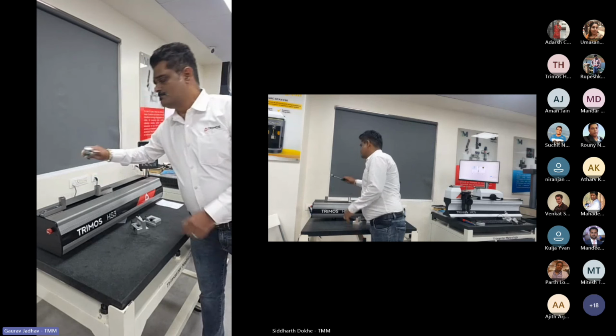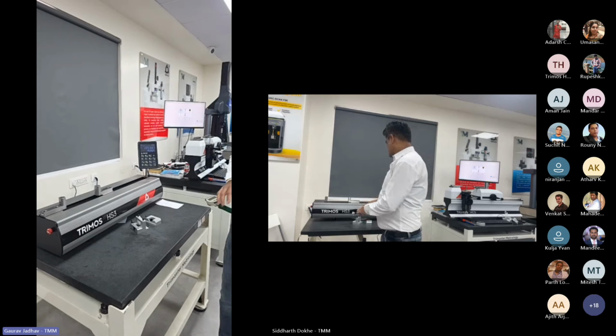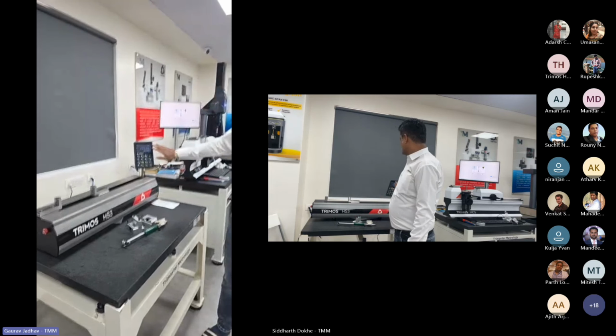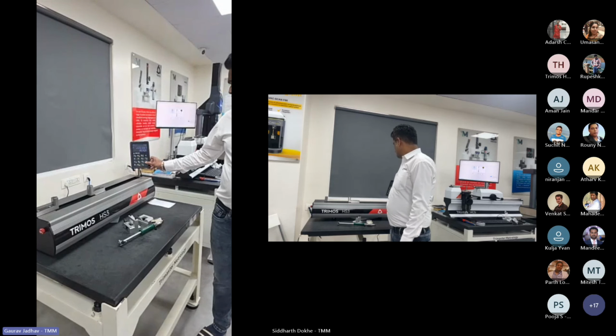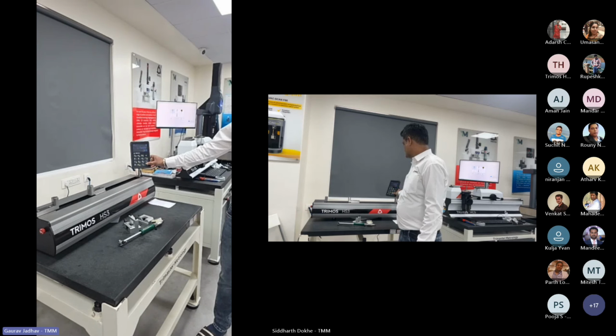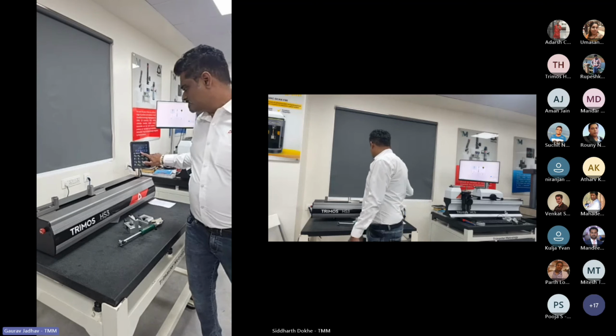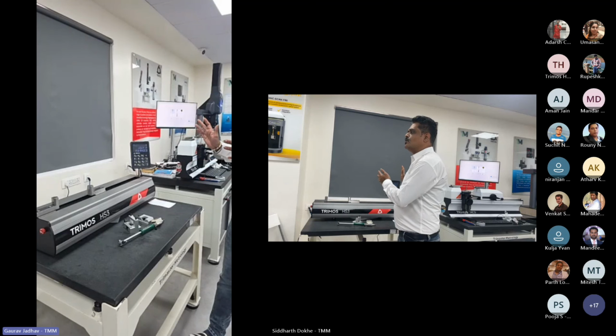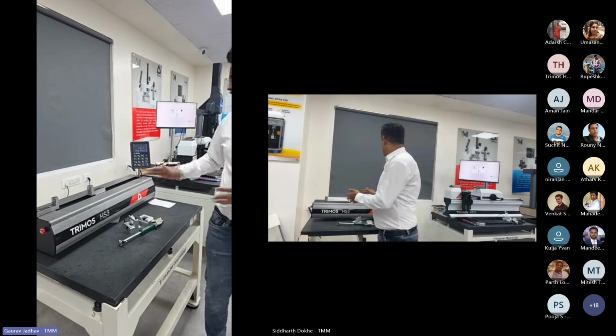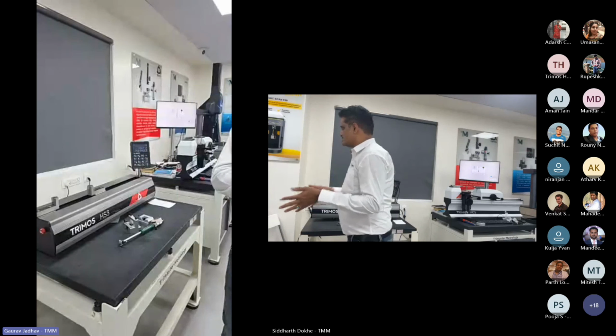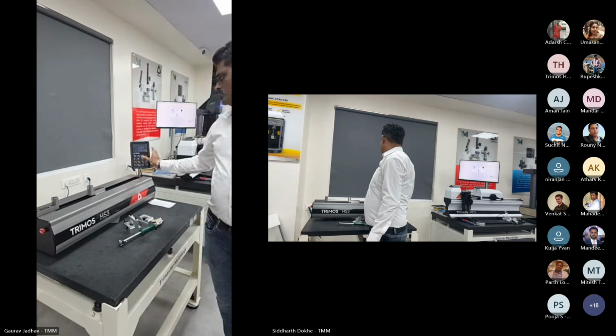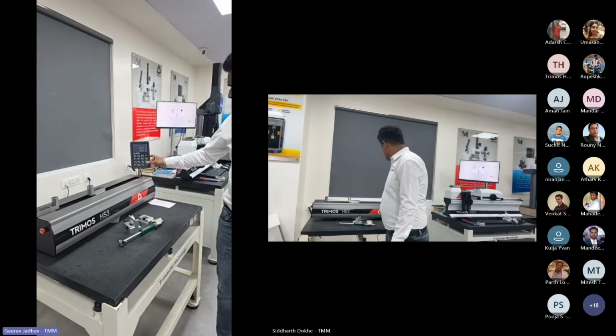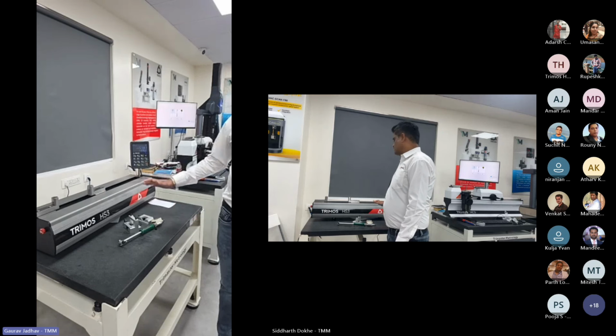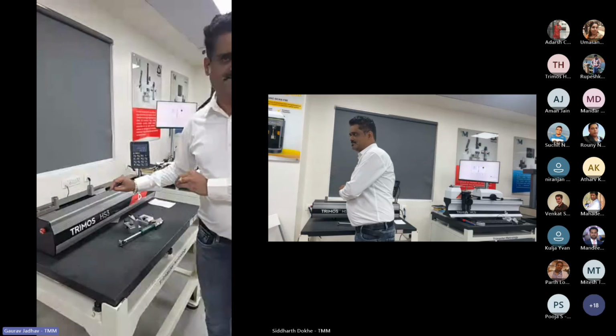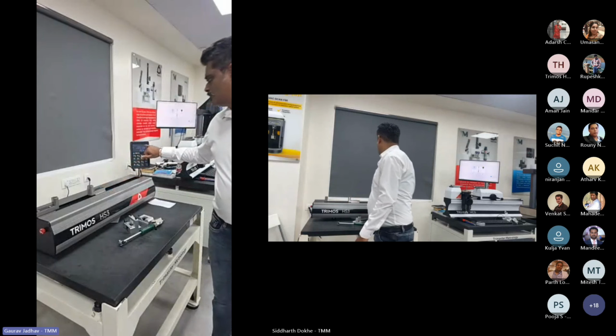Suppose I have some bore gauges with me to set. There are two modes in this machine. I can use the entire function set - if you go to setup, these are the settings. This is 'advanced mode' now, meaning all functions of the machine are open. If you don't want to give all functions to your operators, you can go to normal mode or straight to basic mode. In basic mode, the machine will only work on the position you feed into it. Suppose now the position is 209.706.